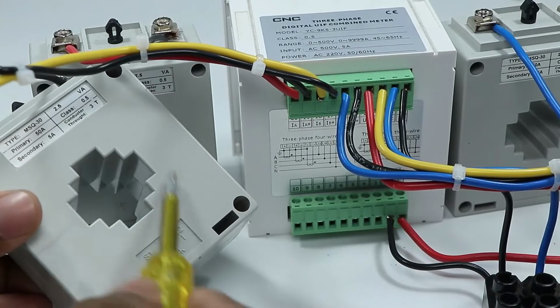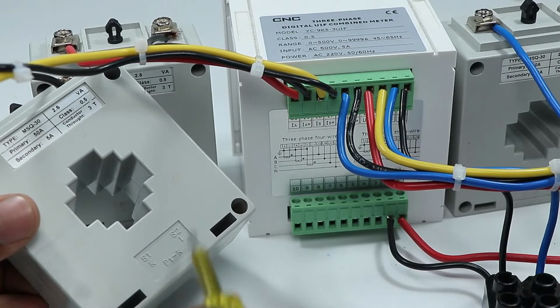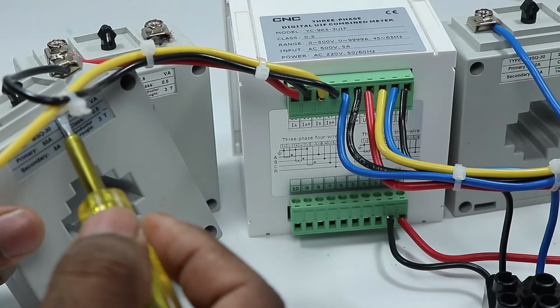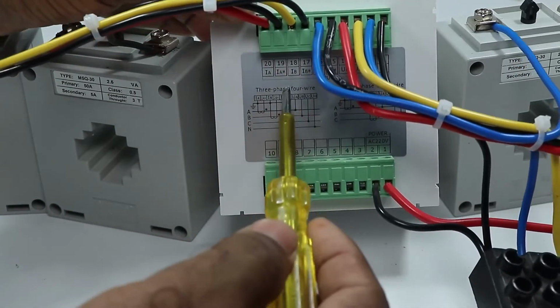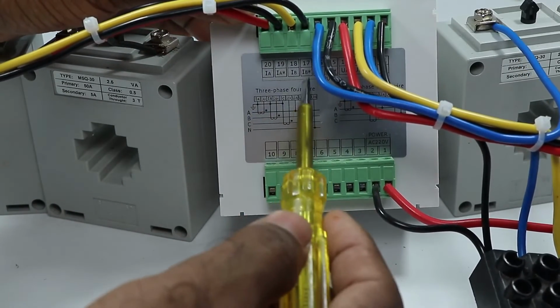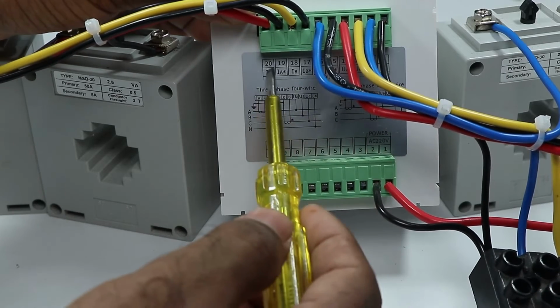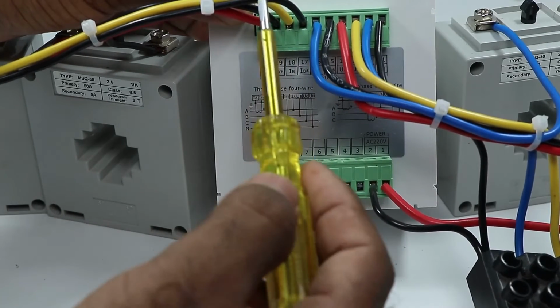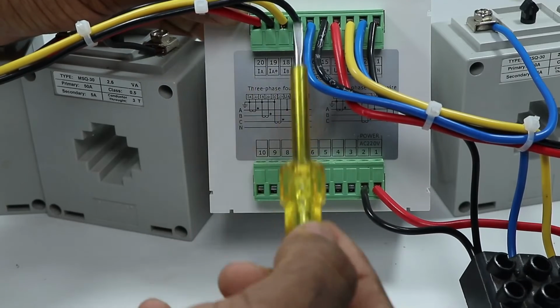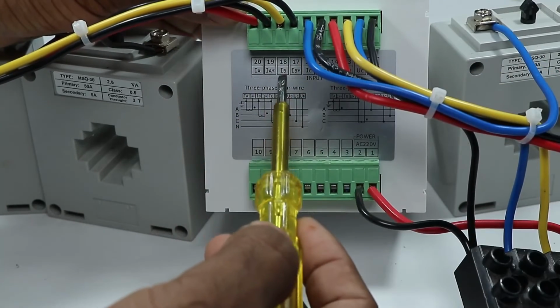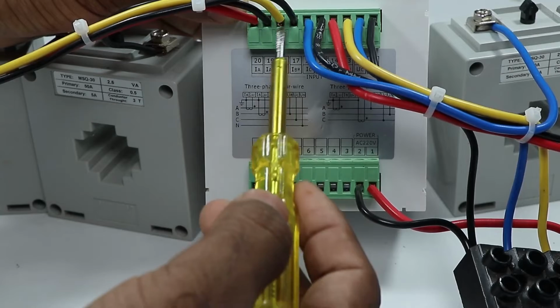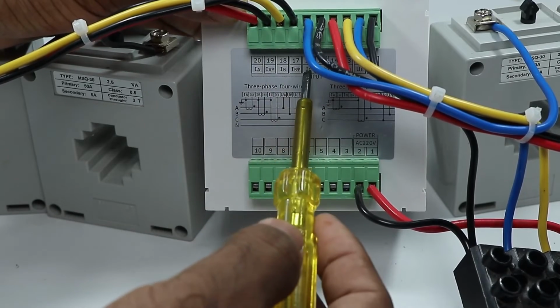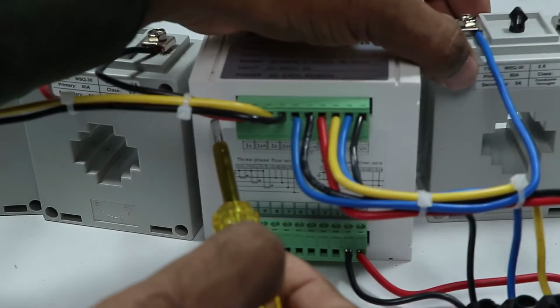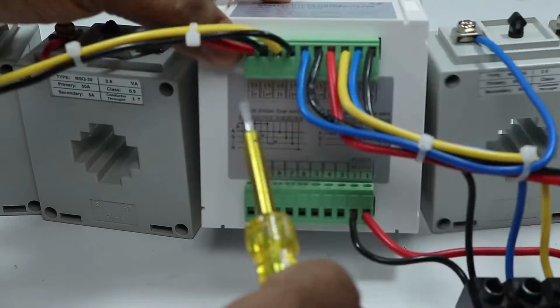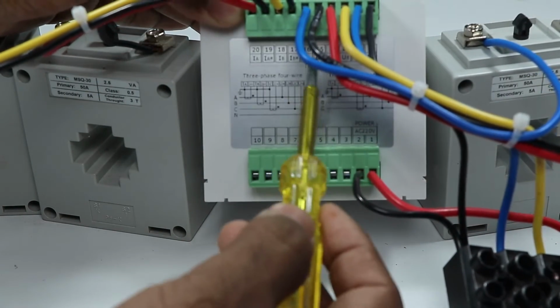Similarly, in the CT used for Y phase, at S1 and S2 terminals connect two wires. Take both wires and connect them at IB and IB star terminals. A means R phase, B means Y phase, and C means B phase power supply. So with IB I connected the wire from S1, and with IB star I connected the wire from S2. Similarly, in the CT used for B phase, I connected wires at IC and IC star.